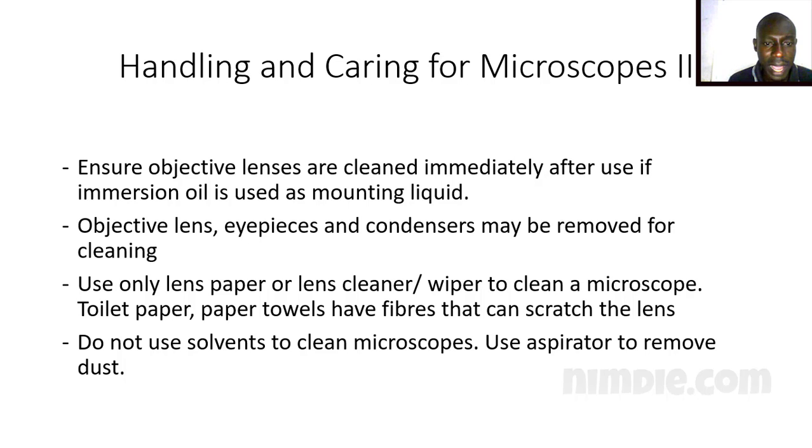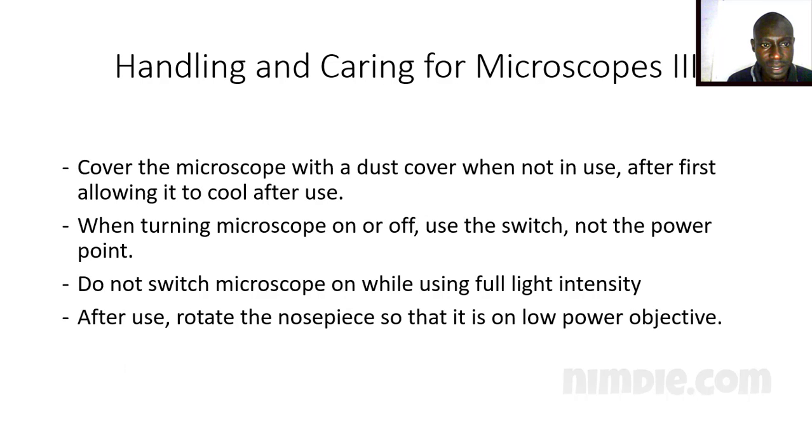Objective lens, eyepieces, and condensers may be removed for cleaning, but use only lens paper or lens cleaner to clean a microscope. Do not use solvents to clean microscopes, and use an aspirator to remove dust. Cover the microscope with a dust cover when it is not in use, but allow it to cool first after use.